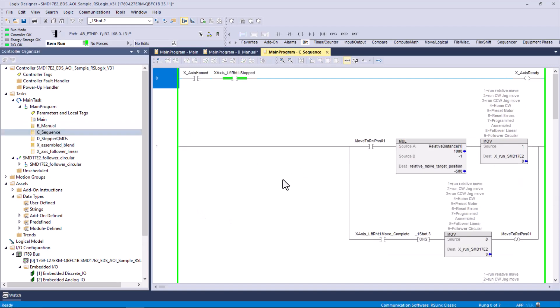In the sequence, I have a rung up here that I've not used yet. If I latch on the bit axis homed and it's stopped, say that it's ready, but I haven't used it for anything yet. Let's take this next rung. I want to do relative position moves. I put in a relative distance. Sometimes people call that incremental. You're going to move in increments. I'm going to move in an increment of 1,000 from wherever I'm at. It doesn't matter where I'm at. It's going to move in an increment of 1,000. Because of the way the encoder is attached to the axes, I have to use negative numbers if I want to move away from home.